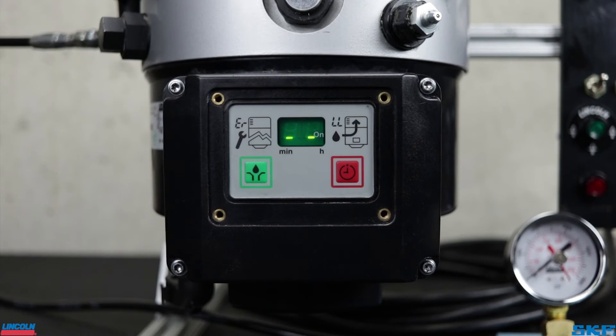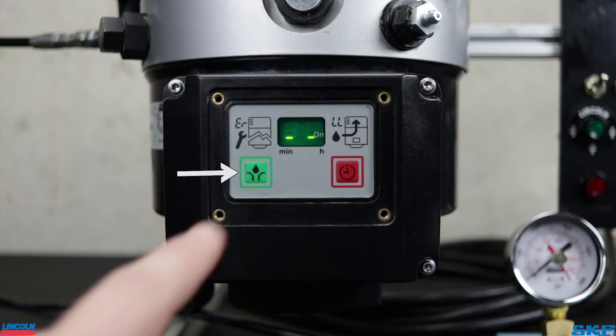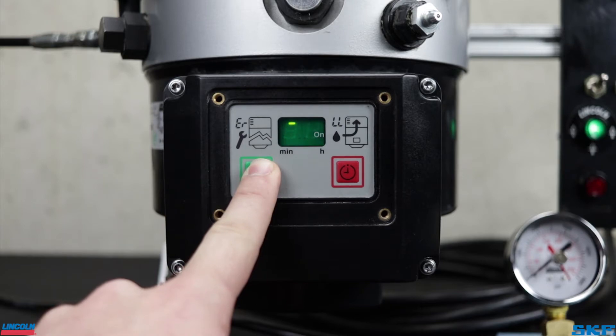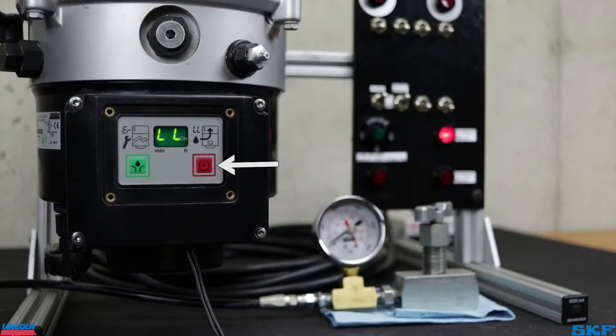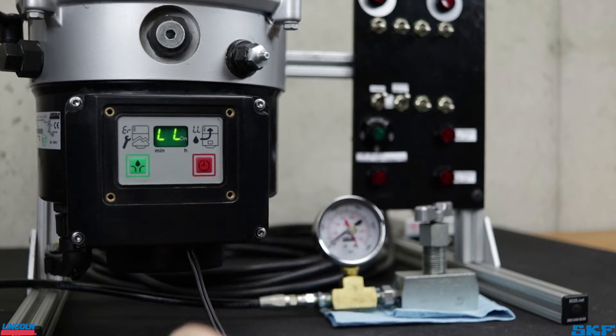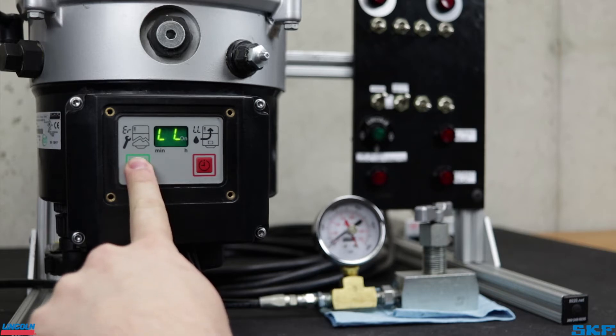Let's quickly go over the layout. Center top of the cover is the screen window — this is where all your codes and programming screens will pop up. The green button to the bottom left is the additional lubrication button. Press and hold this button for four to five seconds to trigger an additional lubrication cycle. The red button on the right is your fault acknowledgement button. If an error occurs, briefly press this button to acknowledge the code. The code will stop flashing and turn solid. Error codes can only be cleared by initiating another lube cycle, which must run through entirely without any issues.